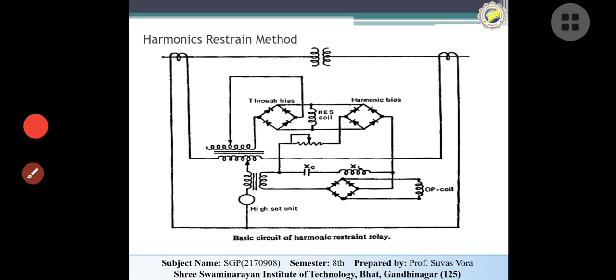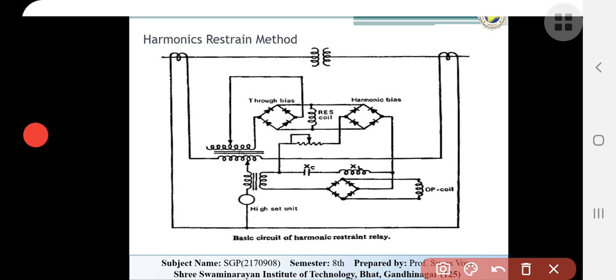So here the first protection system is harmonic restraining. It protects the transformer against the fault but does not operate in the case of the magnetizing inrush current. It consists of a high speed percentage differential protection incorporating a harmonic restraining relay. So it is also called the harmonic restraining differential relay. As I told you before, harmonics affect our transformer and power system, and for this the harmonic restraining method is generally used. This type of relay is sensitive to the fault current but remains inoperative to the magnetizing current.